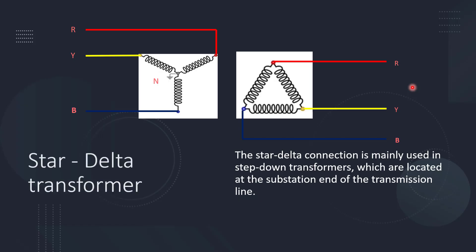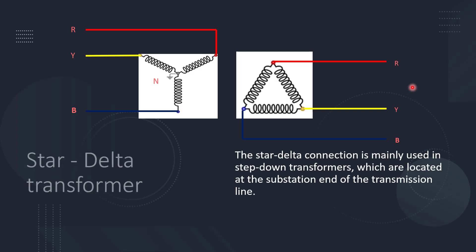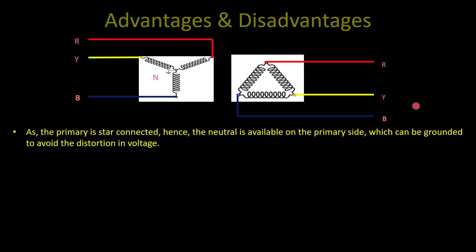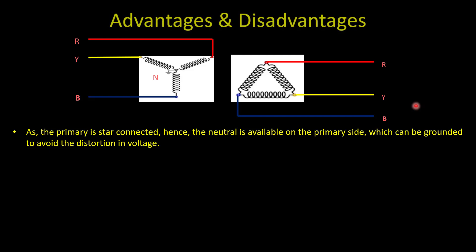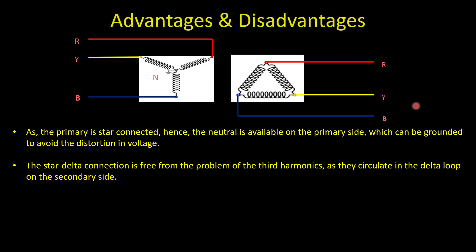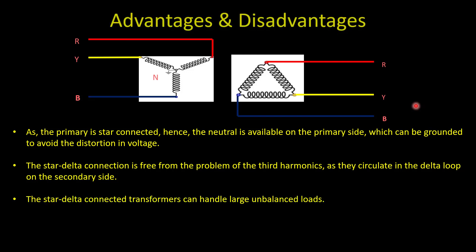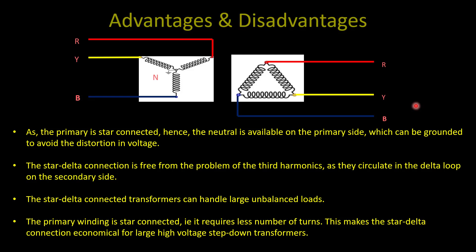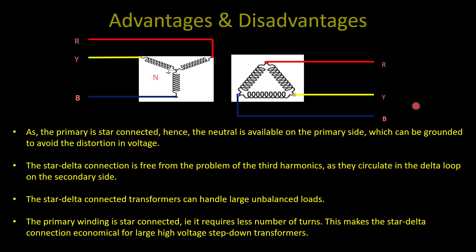Another connection is star-delta transformer. The star-delta connection is mainly used in step-down transformers located at the substation end of the transmission line. Advantages: as the primary is star-connected, neutral is available on the primary side, which can be grounded to avoid distortion in voltage. A star-delta connection is free from third harmonics, as they circulate in the delta loop on the secondary side. A star-delta connected transformer can handle large unbalanced loads. Since primary winding is star-connected, phase voltage is less than line voltage, so fewer turns and less insulation are needed, making it economical for large high-voltage step-down transformers.